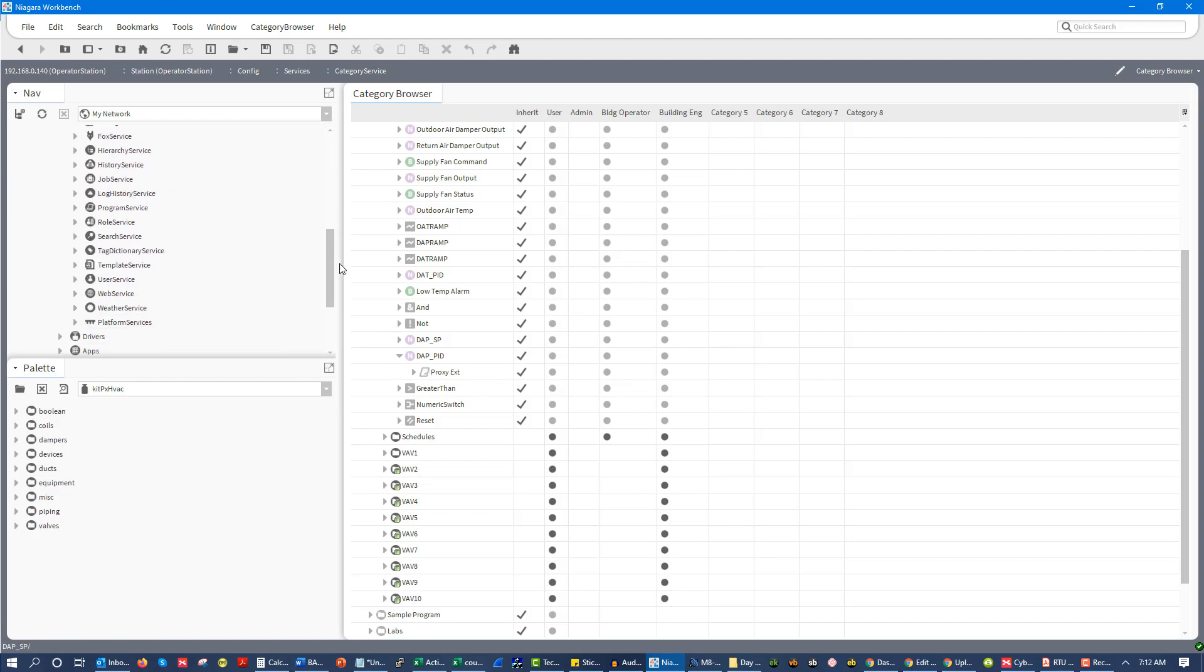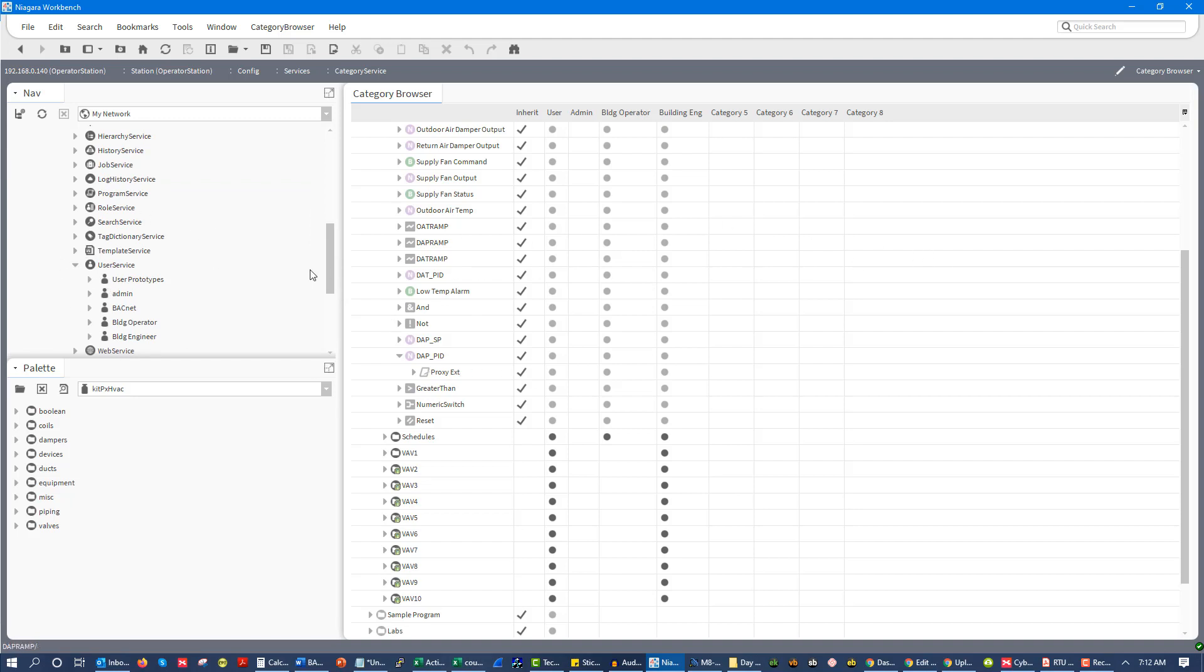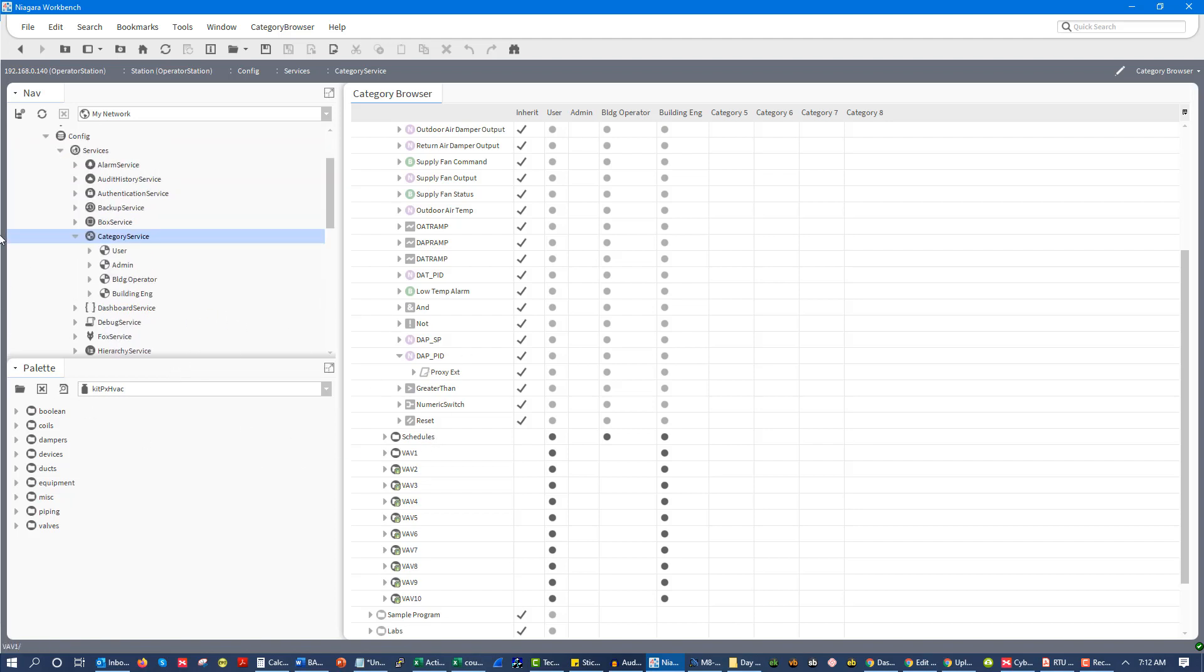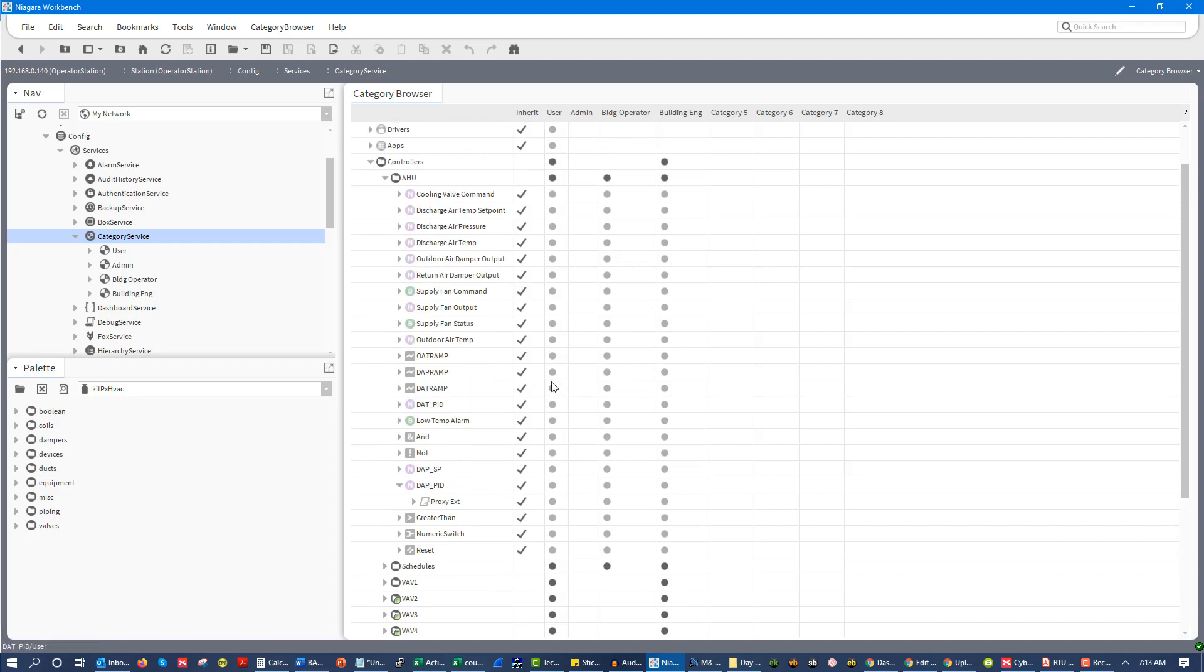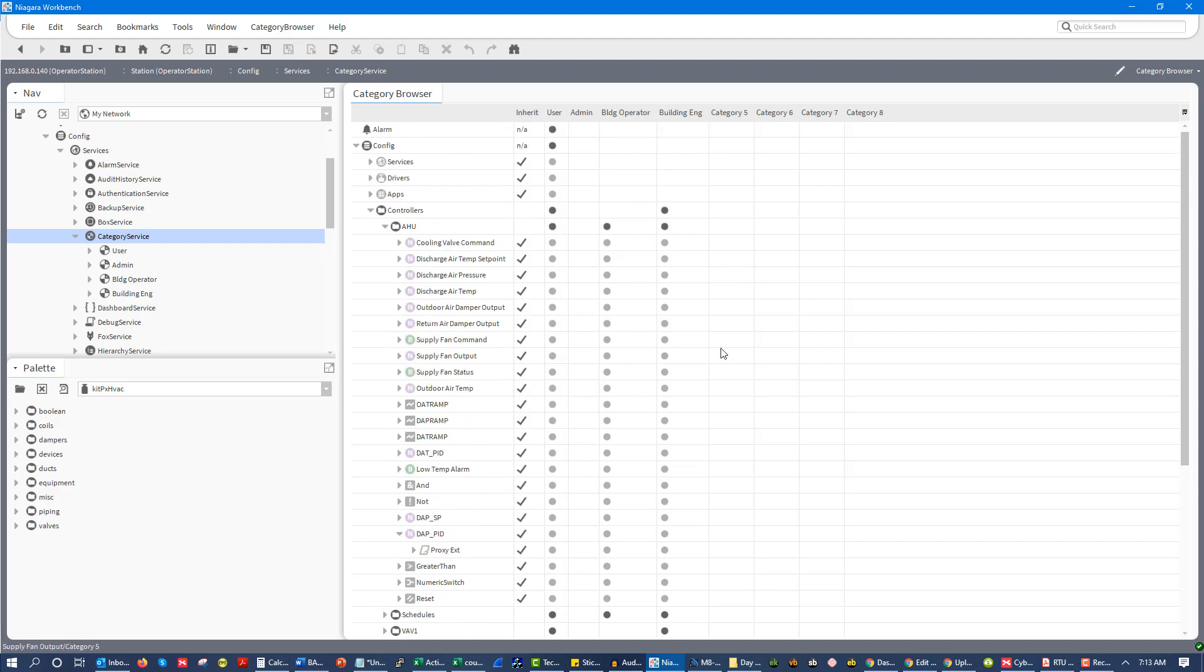So far we talked about the importance of setting up unique users for everyone. Fortunately, you can integrate with the customer's active directory so that they can use the same user account. Not with every building automation system, but with most, you can interface with their active directory and use the same user accounts that they use to log into their daily work. If you don't have that capability, then you should really set up a user for each user using unique passwords, forcing password policies. Once all that's done, then we set up our categories or permissions. For some folks using Niagara, it's going to look like this screen. For others, you're going to have where you actually set it on individual points and pick categories. There's a variety of different ways of setting it up. The important point is that you actually set it up.